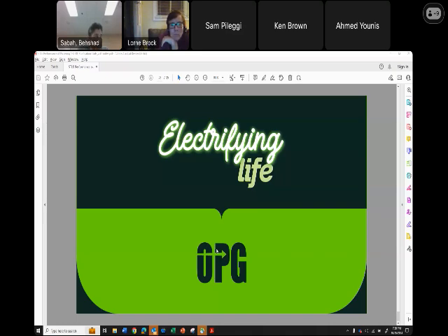We tried a similar thing at Darlington on unit two, where we replaced the screw pumps with swashplate axial piston pumps, but the design of that project was not sufficient, and they're basically running the swashplate axial pumps as constant volume pumps, and they're not improving their EHC condition because of that. So there are things being tried. Yeah, it just takes time and money and effort.